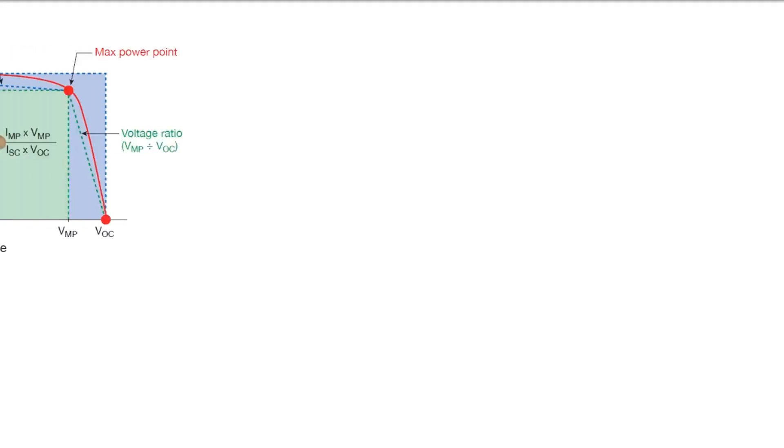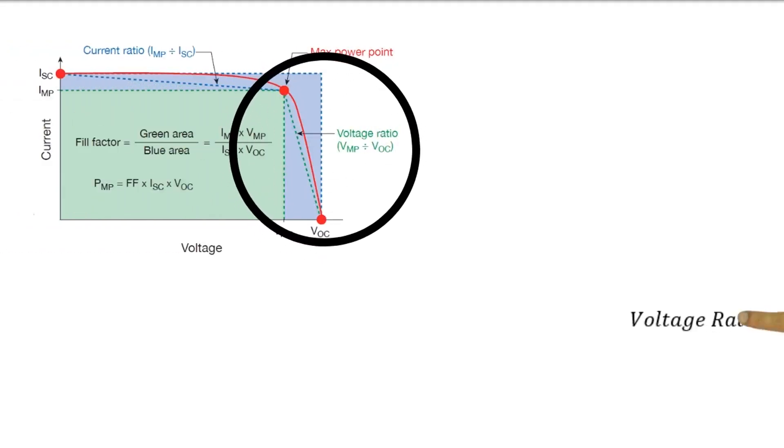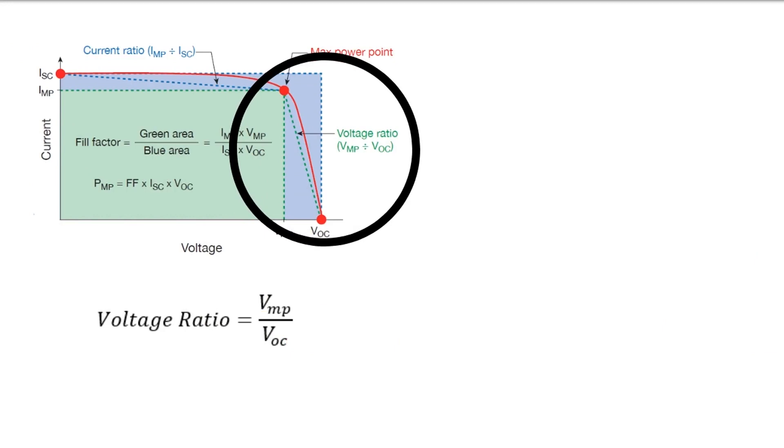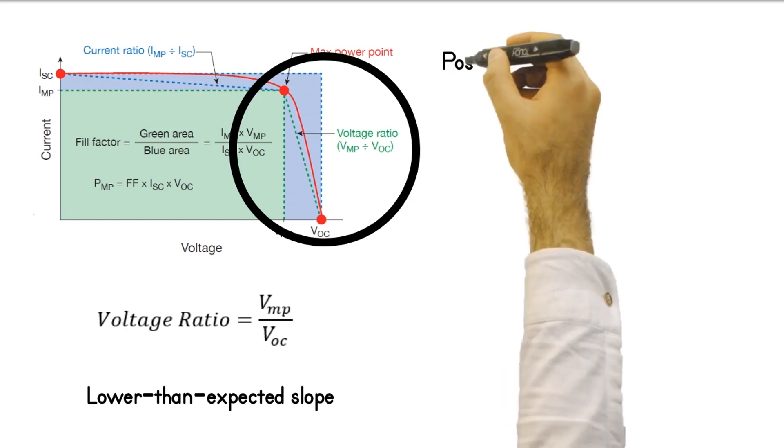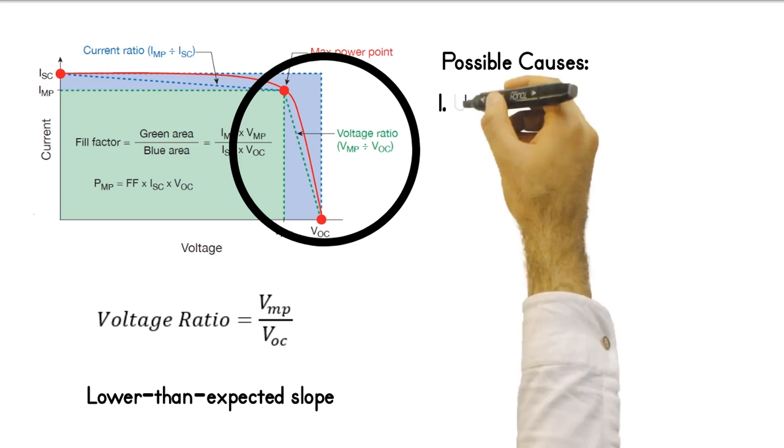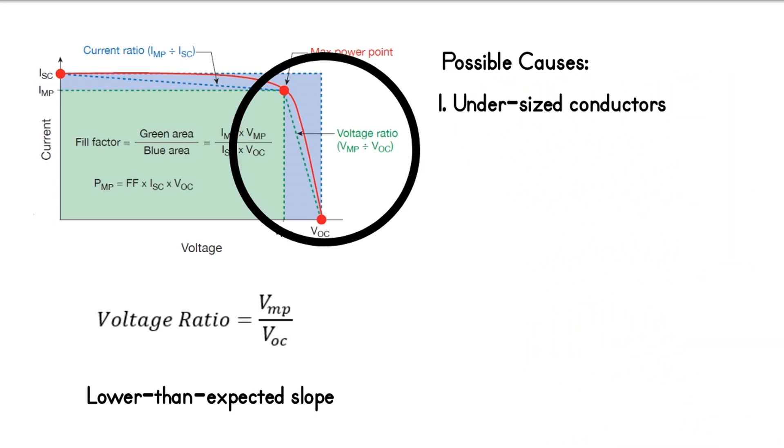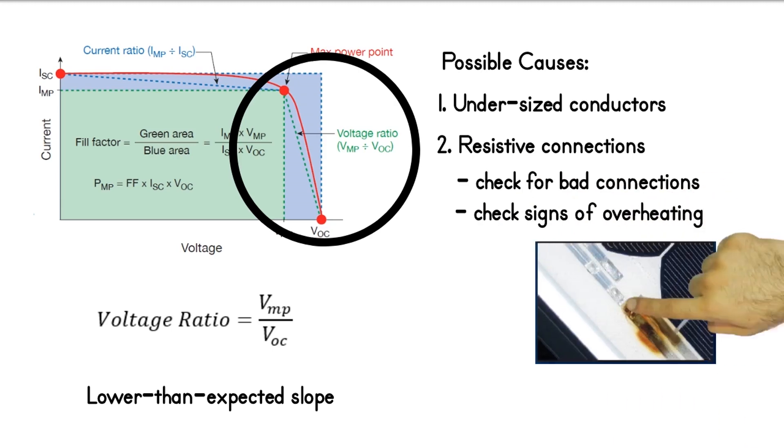The fifth type of deviation is low voltage ratio. Voltage ratio is the ratio between the voltage at maximum power point VMP divided by the open circuit voltage VOC. It is characterized by the lower than expected slope in the vertical portion of the curve when compared to the curves of other strings. Some of the likely causes of low voltage ratio are undersized PV source circuit conductors, resistive interconnection, or module degradation.